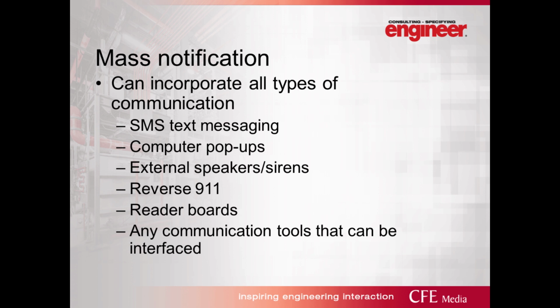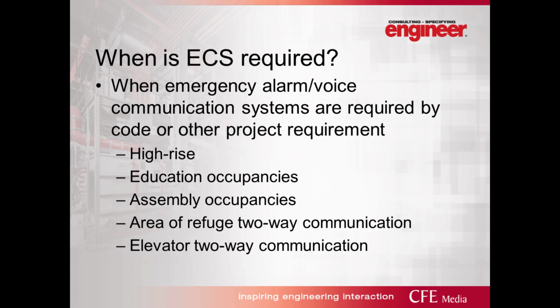So there is now a UL standard on mass notification. It's 2572. Almost all the major fire alarm manufacturers have had their emergency communication or their evac systems dual listed at this point, so their fire alarm panels are both listed for mass notification as well as fire alarm. Now, that doesn't mean that you can't also incorporate other means of communication. You can have your mass notification system trigger text messaging or computer pop-ups or external, what we call wide area speakers or sirens to warn people outside of buildings. You can trigger a reverse 911 system or have reader boards activate to give information to your occupants. Any communication tools that you have can be interfaced as part of a mass notification system.